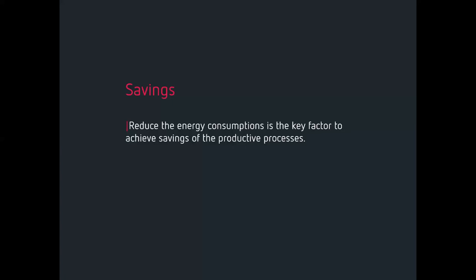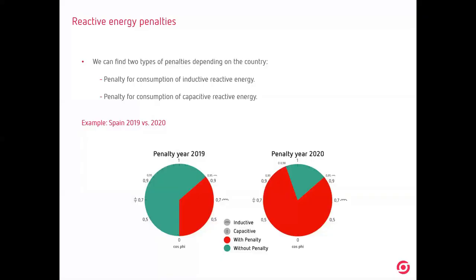We will make a webinar regarding these products, okay? But savings, reducing the energy consumption, is the key factor to achieve savings in productive processes. It means that by installing capacitor banks, if we have penalties, we will reduce the bill at the end of the month, okay? And we can have two types of penalties depending on the country: penalty by consumption of inductive reactive energy or capacitive reactive energy. Okay, it depends on the country. In Spain, we used to have inductive, but this year we will also have capacitive.